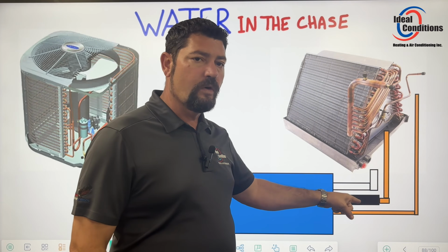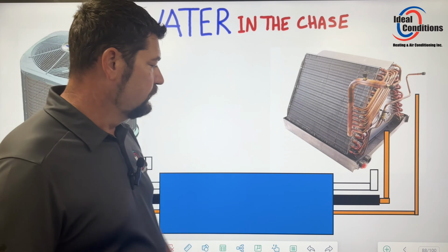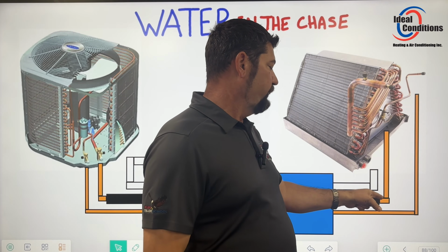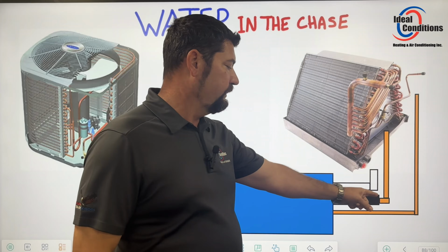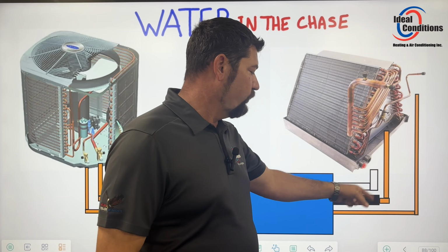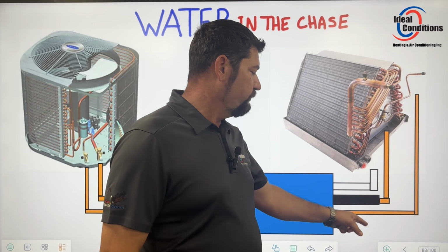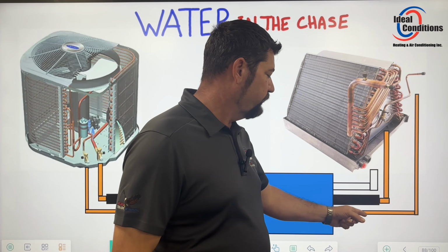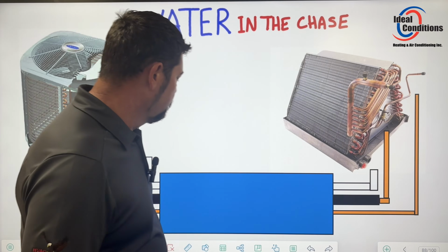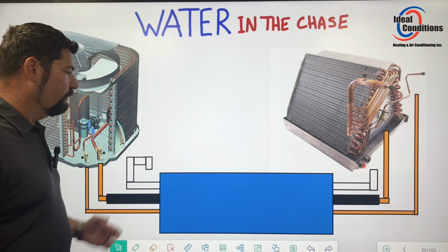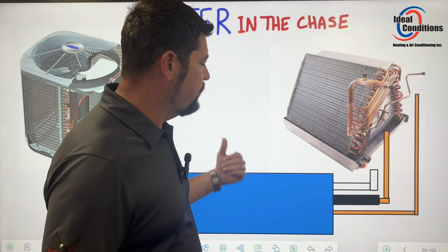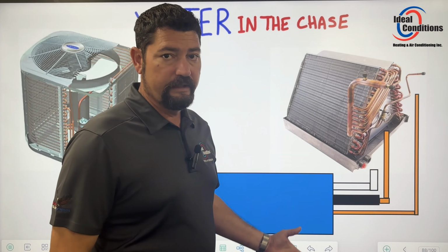So you don't want 1/2 inch wall on your pipe, because you're going to add an additional 1 inch on top of the diameter of the copper already. So between that might already be 7/8 of an inch, and then you're adding another 1 inch of Armaflex, 1/2 inch on both sides. So now you have 2 inches there, plus you have the liquid line, plus you have 3/4 inches of PVC, and your chase is never easy to run all that through. So a lot of people just think, oh, I'm not going to run Armaflex on my copper. So what happens is they wind up running no Armaflex, and that's not good.